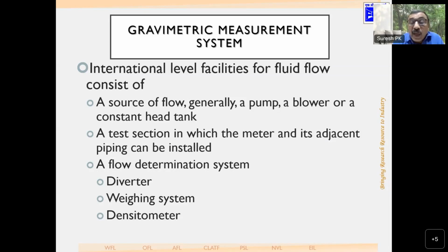A test section in which the meter and its adjacent piping can be installed. After the tank, supposing that the source of flow is a tank, you need to have a test section in which the meter and its adjacent piping can be installed. Meter installation needs upstream length, downstream length, a system to remove the air. All these things are required in the calibration system, and proper assembly. Proper assembly means the assembly of the meter as per the manual of the meter.